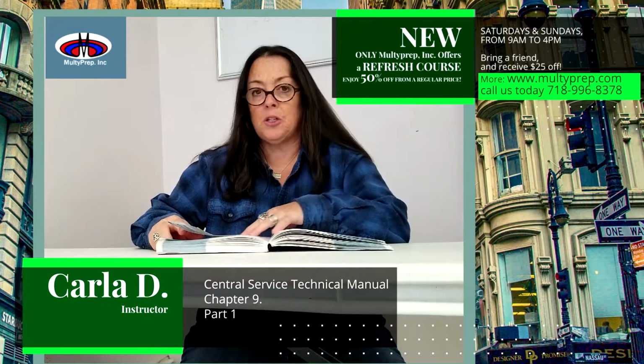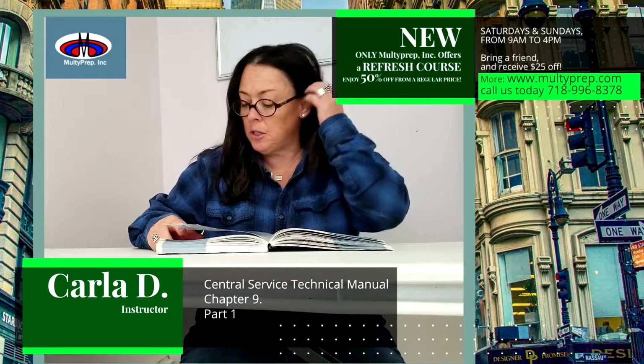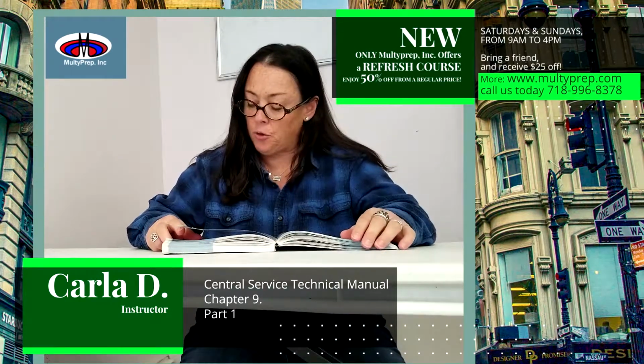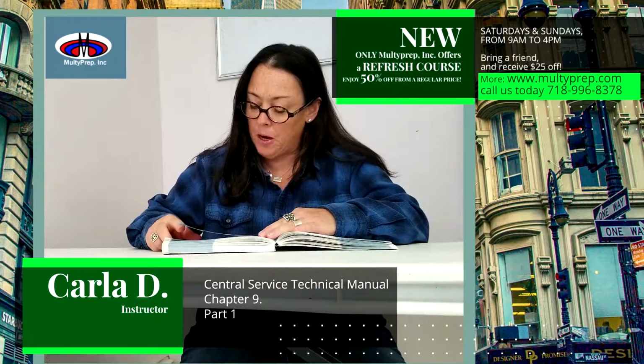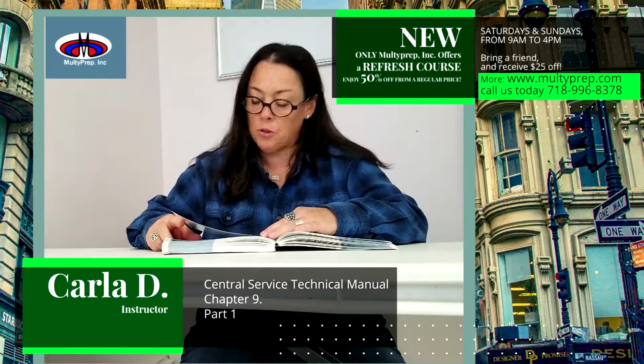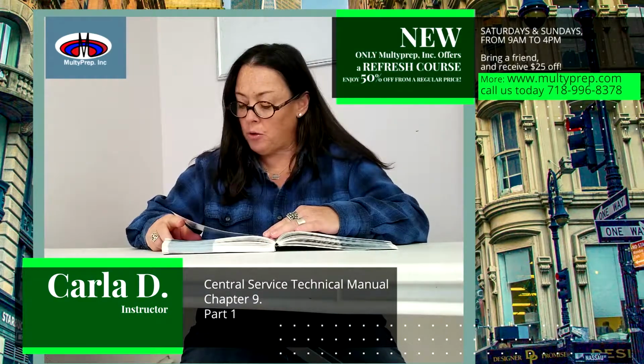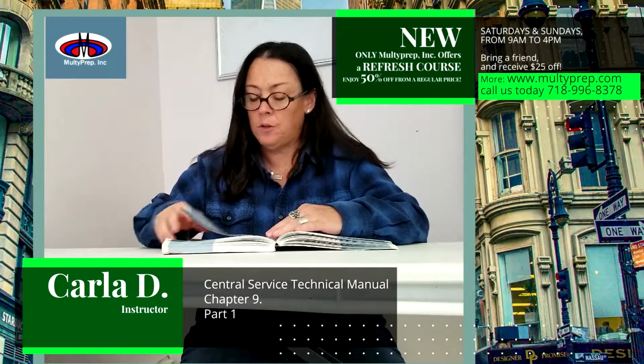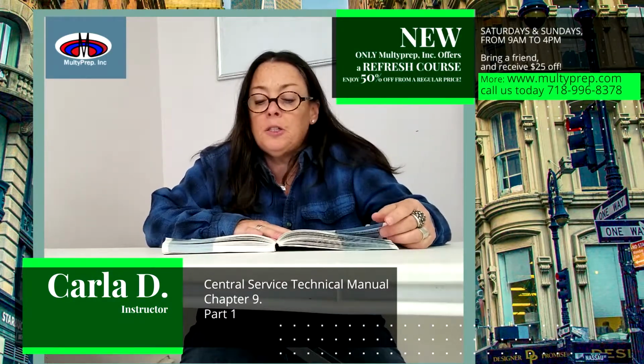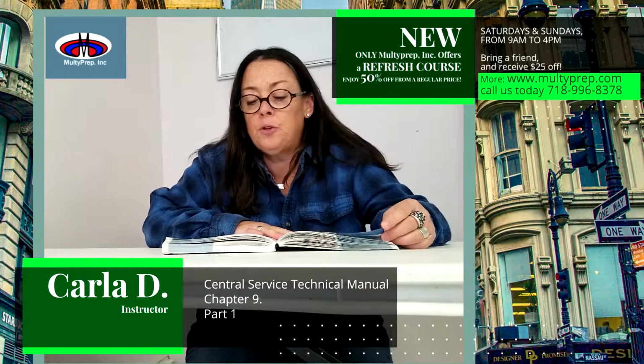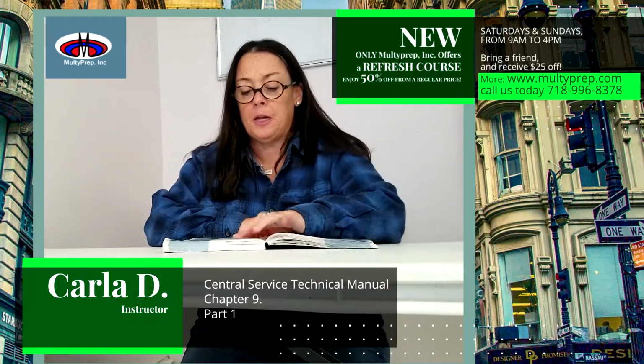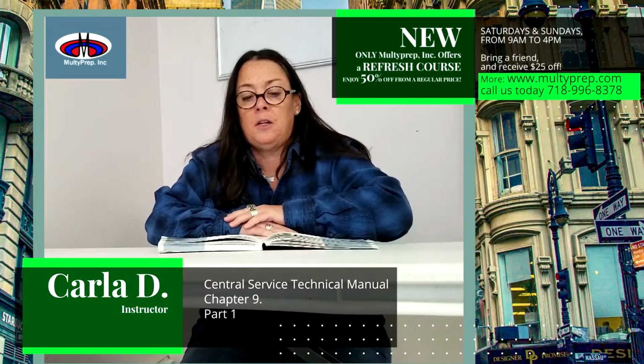Back to page 165. Stainless steel instruments should not be subjected to strong phenolics for a prolonged period of time because phenolics can be corrosive. Some plastics also react poorly to phenolics. Follow the device manufacturer's instructions for use for the types of materials that can withstand disinfectants and phenolics.